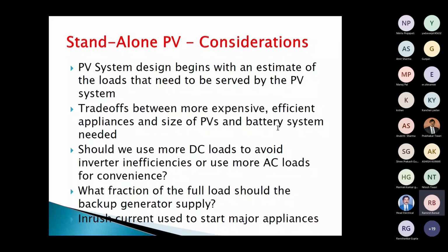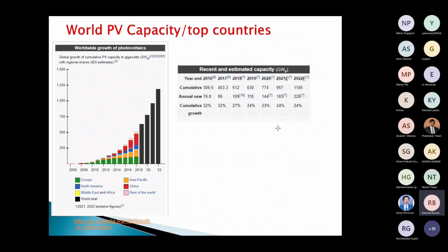Okay. Then, what fraction of the full load do we have the backup generator for? Because if you have 100% backup, the generator size will increase, and that will add to the cost as well. And then we also have to see what kind of load we have: either all static load, or dynamic load as well, like motor load. And for motor load, you also have to keep the inrush current condition in mind. Okay, so I'm trying to quickly cover as much as I can.